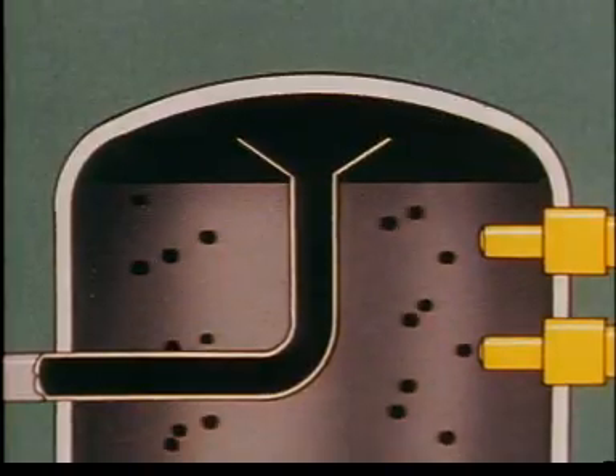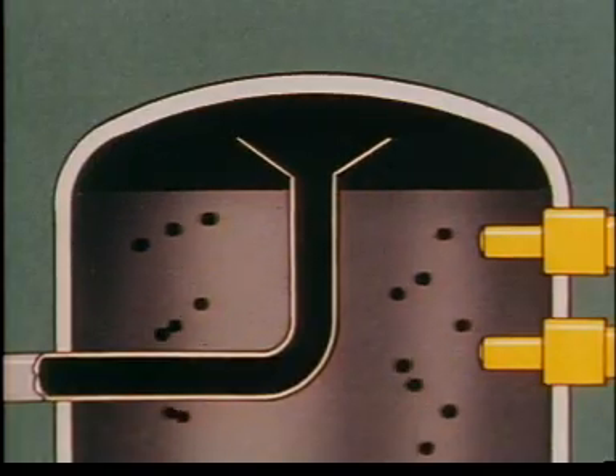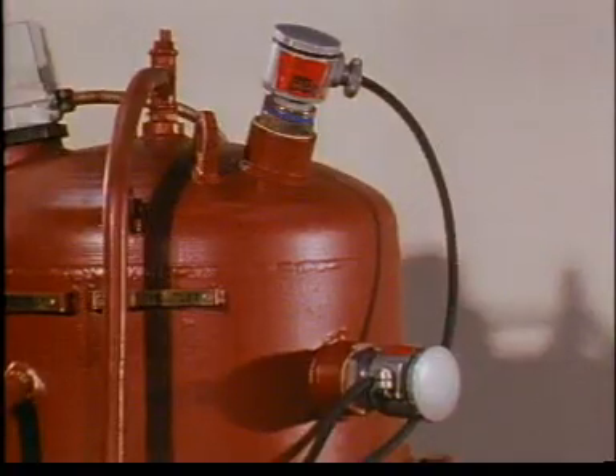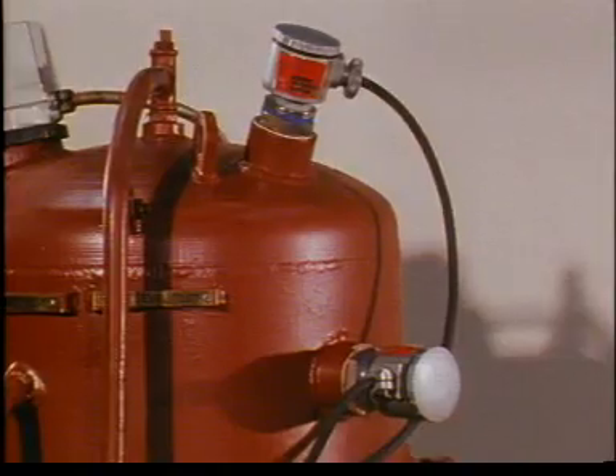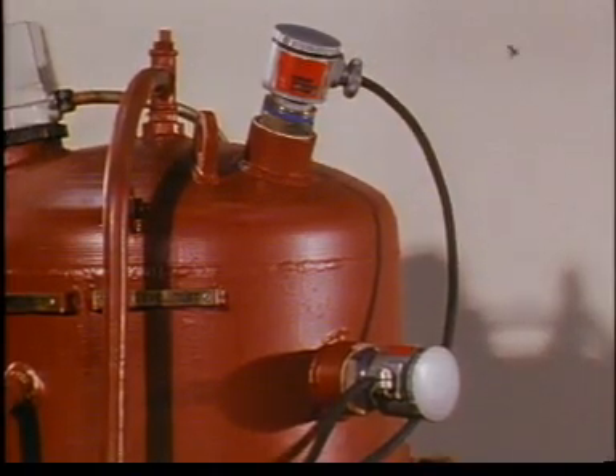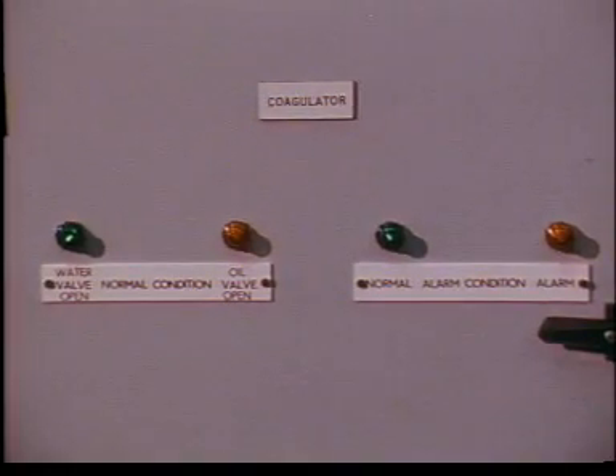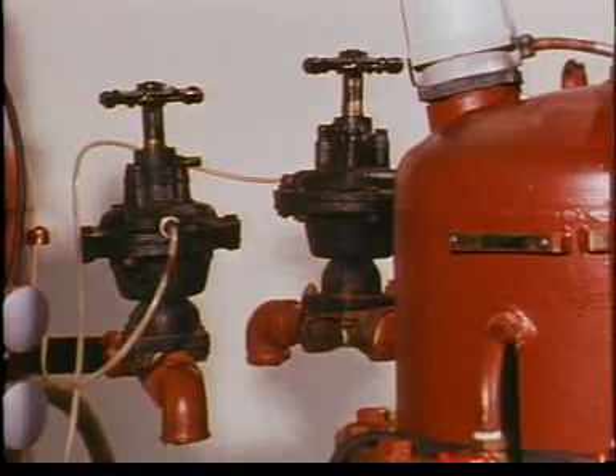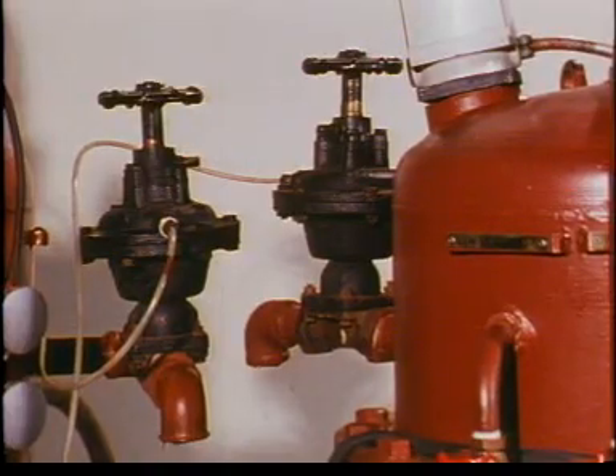The oil collects in the top dome in a similar manner to the separator. On the coalescer, however, there are only 2 probes. The upper probe initiates a signal which opens and closes the oil outlet valve. It is closed when the probe is immersed in water and a water indicator light is illuminated on the control panel. Clearly, if the upper probe is immersed in water, so will be the lower probe, and its water indicator light will show on the control panel. In this condition, the outlet valve is closed, so no oil flows to the storage tank.